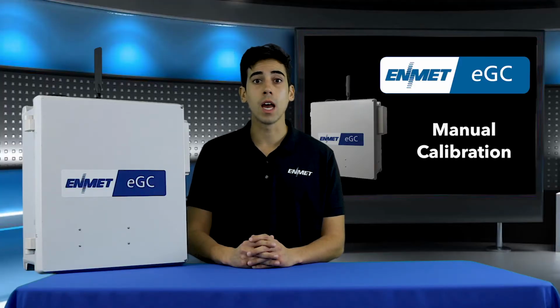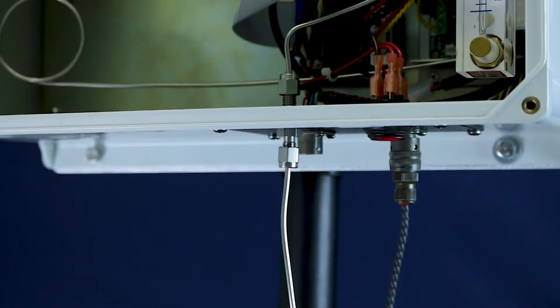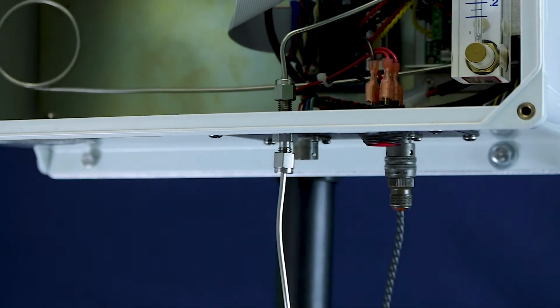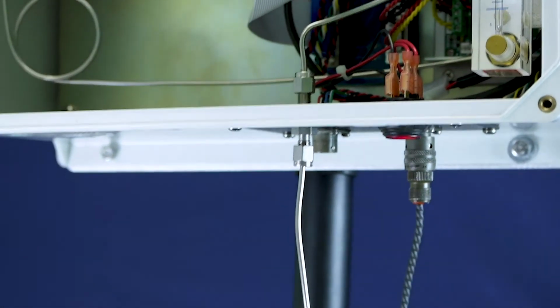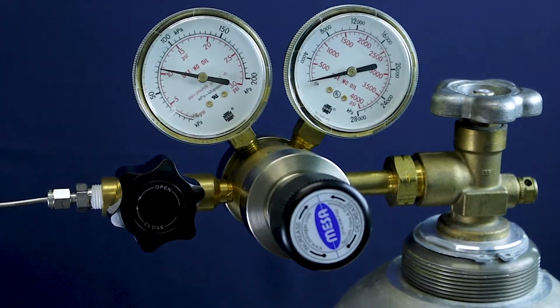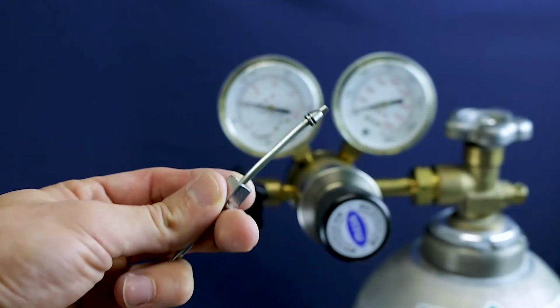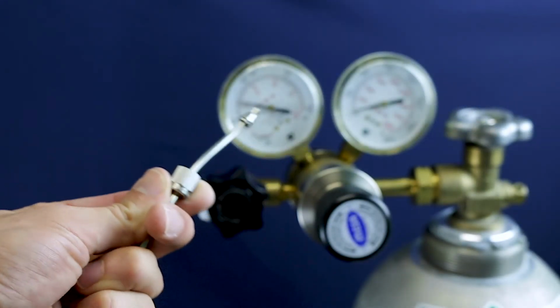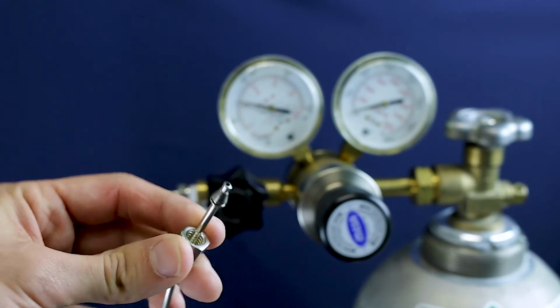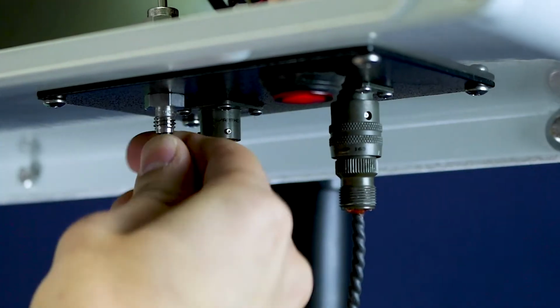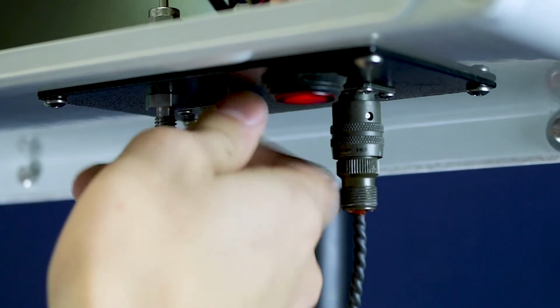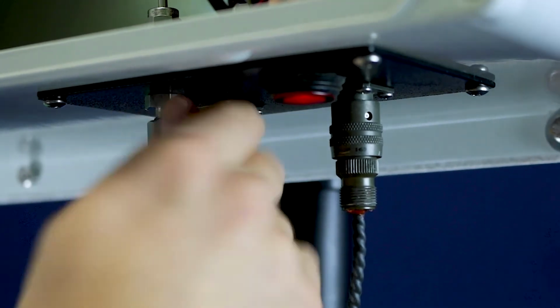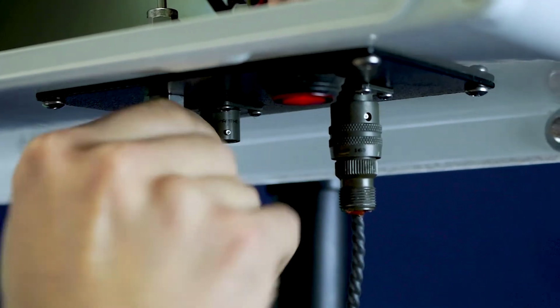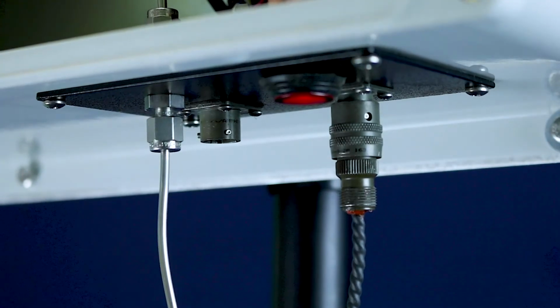Before you start the calibration, you must connect the calibration gas inlet Swagelok fitting on the power entry plate to your 10 parts per billion calibration gas cylinder using the length of 1/8 inch OD pre-cleaned stainless steel tubing. Make sure you do not over-tighten your Swagelok fitting. We suggest after the nut is finger tight, you tighten the nut with a wrench by no more than 3/4 of a turn.